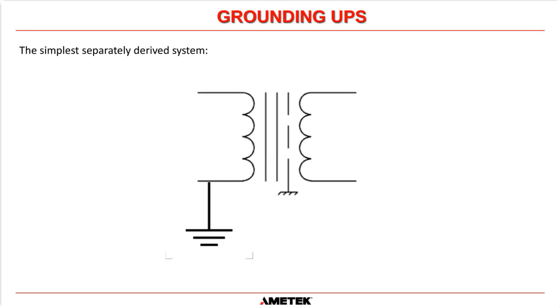And as you can see here on the primary winding, the neutral will be connected to ground as part of the distribution system, either the MCC, or if it was in your home, it would be your breaker panel outside your house. Okay, but what's important to understand is the secondary side, as drawn here, has no ground connection. So that's where the term separately derived system comes from, that the secondary in this case of the transformer has no connection at all to the building electrical work, okay?